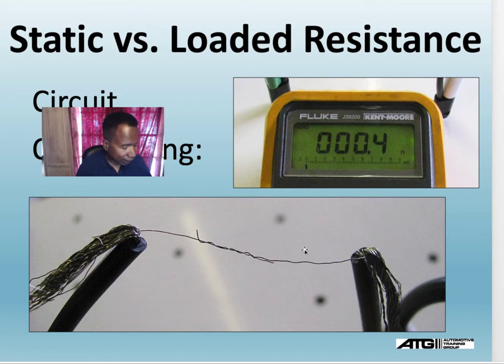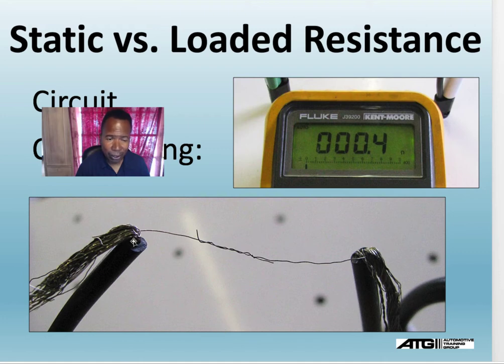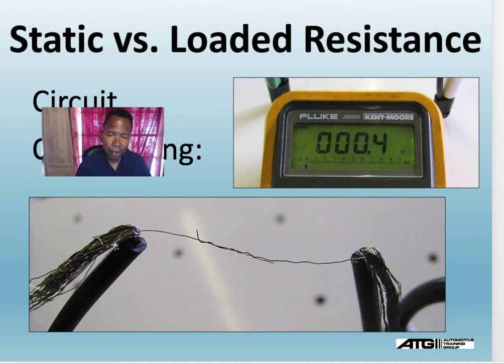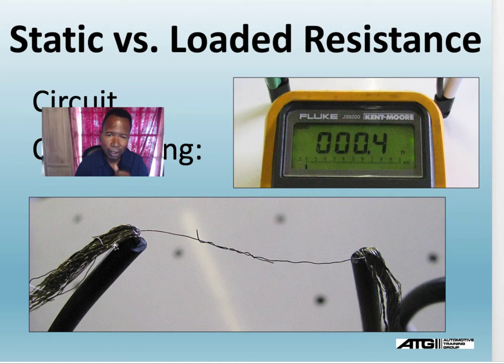It's just like a loose connection — loose terminals — all of those cause high resistance. A strand of wire like this that's supposed to be connected to the rest but isn't will also cause a high voltage drop and high resistance. High resistance is caused by a strand of wire like you see here, loose connections, and corroded connections.